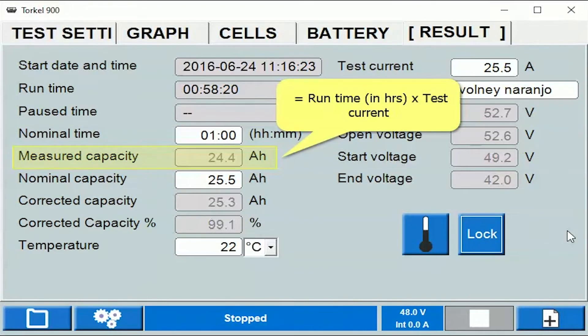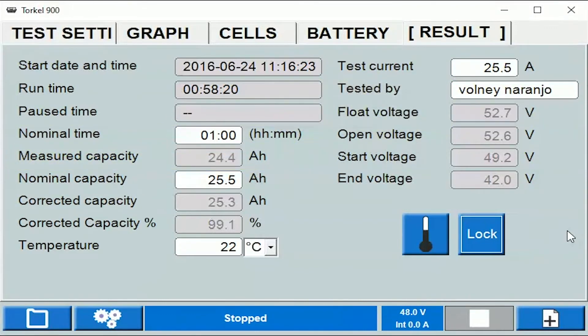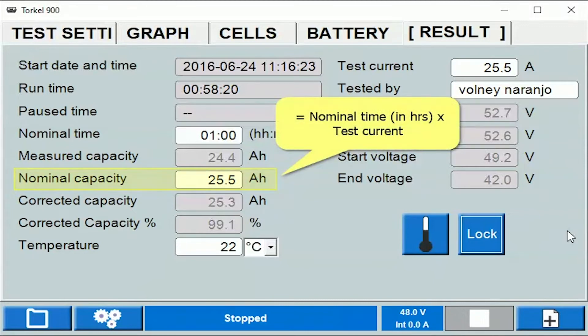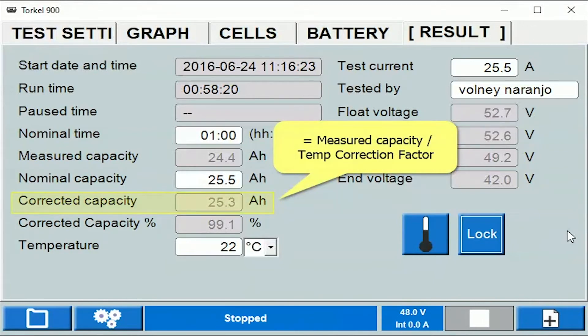Nominal time is the intended duration of the test. Test measured capacity is test current times the runtime. Nominal capacity is not the rated capacity of the battery — it is test current times the nominal time.